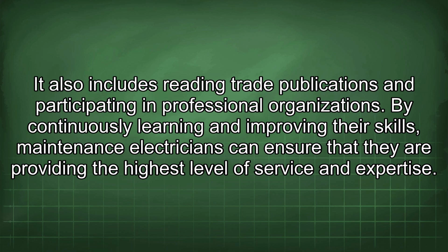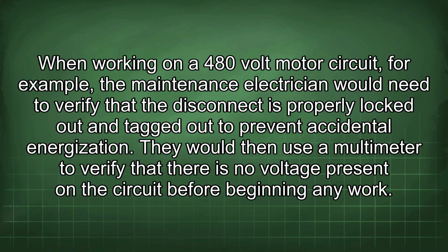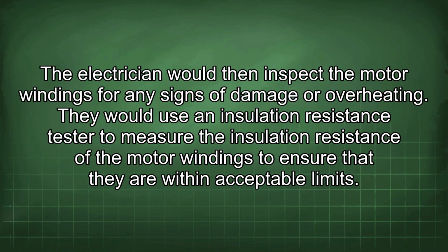and expertise. When working on a 480-volt motor circuit, for example, the maintenance electrician would need to verify that the disconnect is properly locked out and tagged out to prevent accidental energization. They would then use a multimeter to verify that there is no voltage present on the circuit before beginning any work. The electrician would then inspect the motor windings for any signs of damage or overheating.